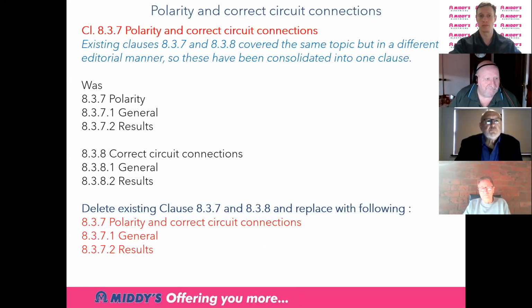Next slide. Oh, the good old one you can really blame Roy for. Polarity and circuit testing. Okay, how can you have an incorrect or reverse polarity, as it's commonly called, if you don't get your connections wrong? Had me confused for quite a while. So I won the committee over, and what we've done is actually combined two of the tests. So now when somebody stands in front of you and says, how many mandatory tests? You don't say 6 anymore, you go 5. Good answer. Okay, so we've amalgamated the correct circuit connections and polarity into one. Next slide, please.